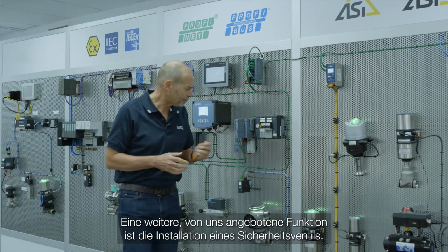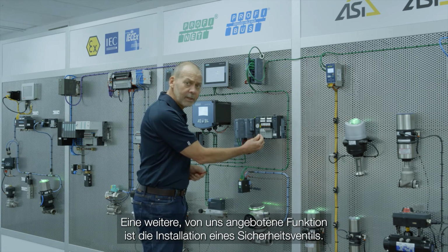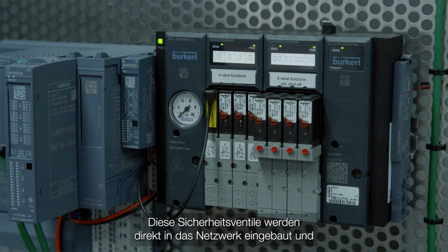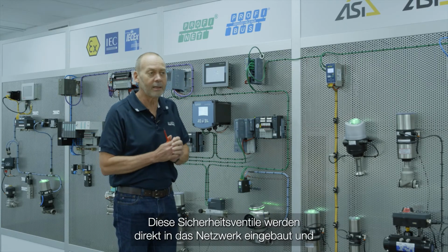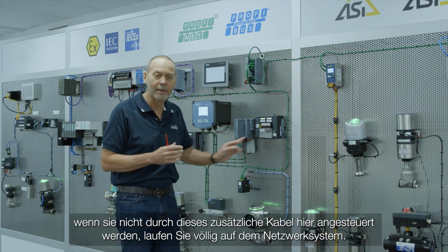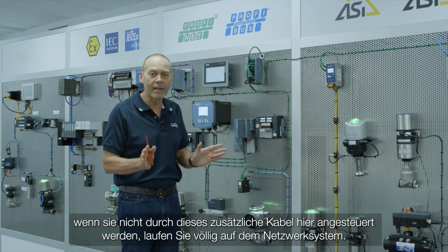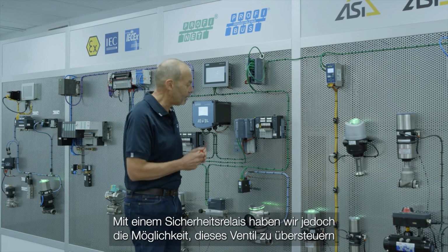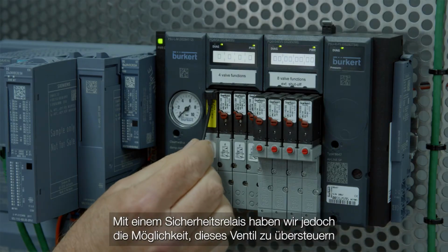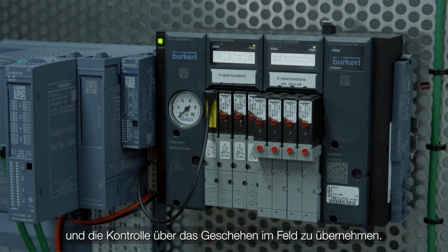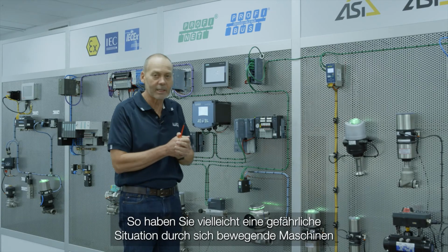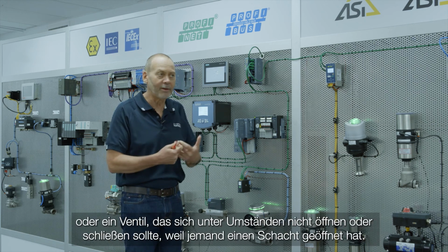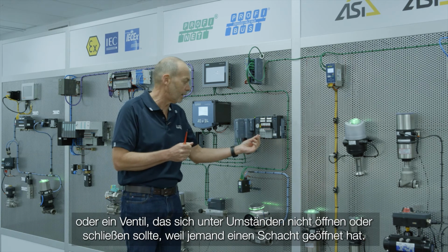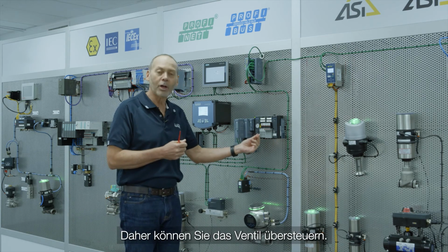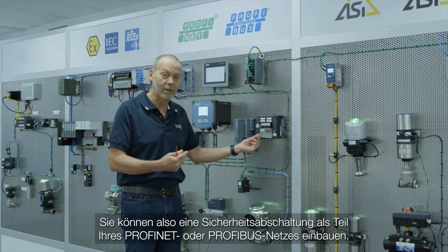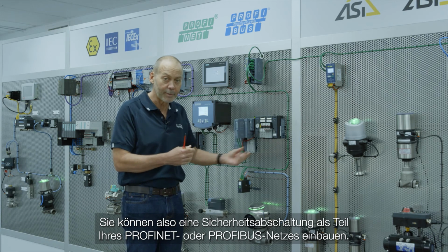Another feature that we offer is the ability to have a safety valve installed as well. These safety valves mount directly into the network, and when they're not overridden by this extra cable here, they are fully running on the network system. However, we have the ability with a safety relay to override that valve and take control of what's happening in the field. So you may have a dangerous situation from moving machinery, or a valve that shouldn't open or shouldn't close because someone's opened a manhole. Therefore, you can override the valve. So you can have a safety circuit as part of your PROFINET or PROFIBUS circuit.